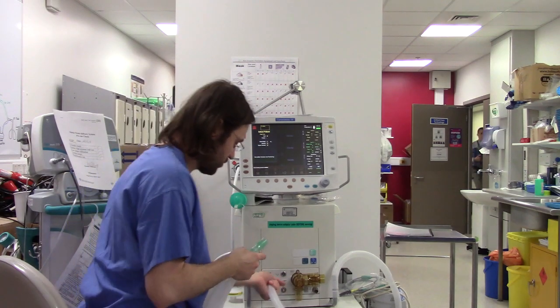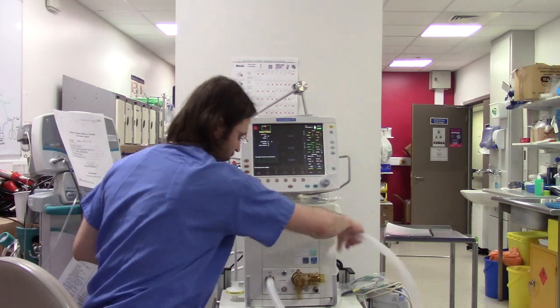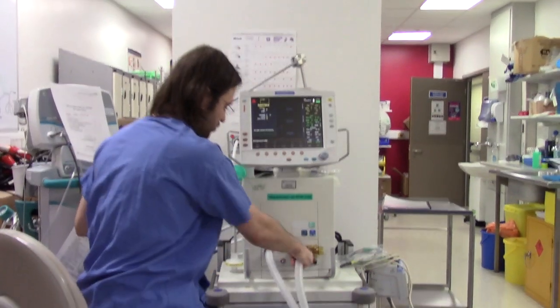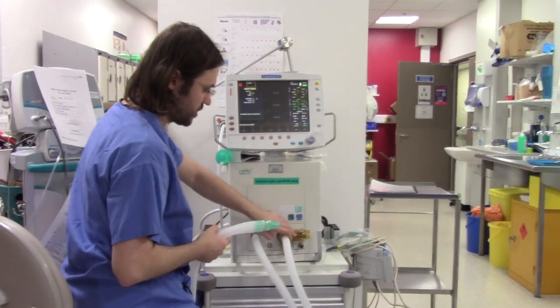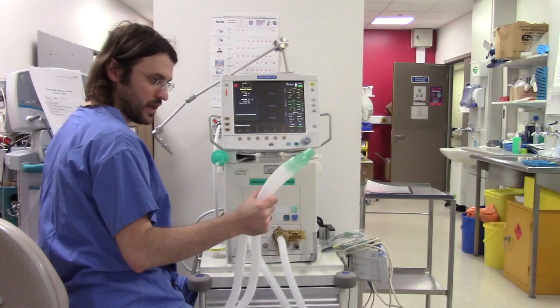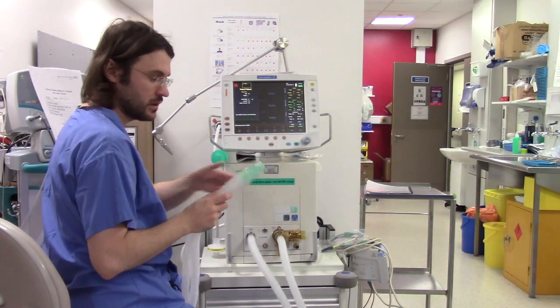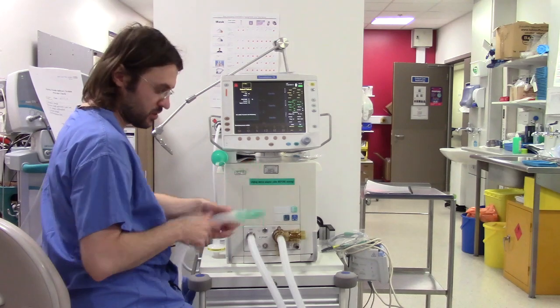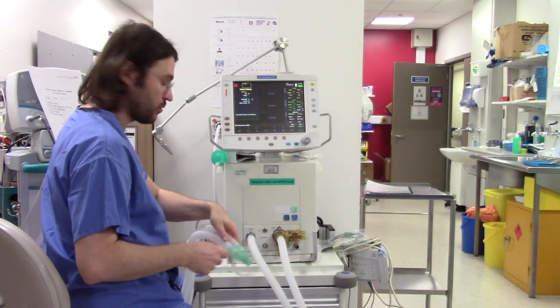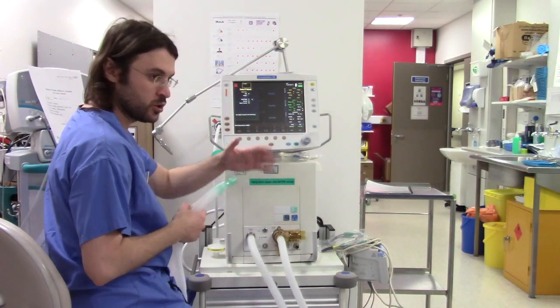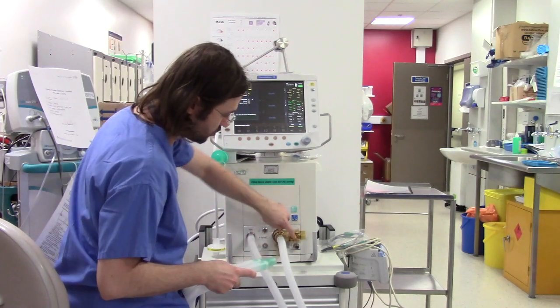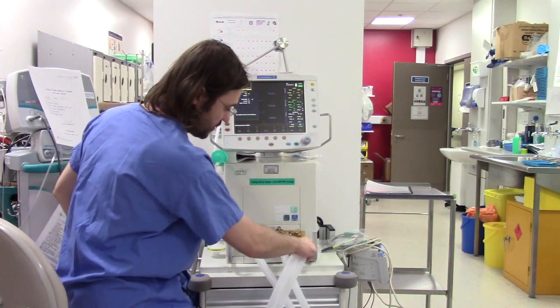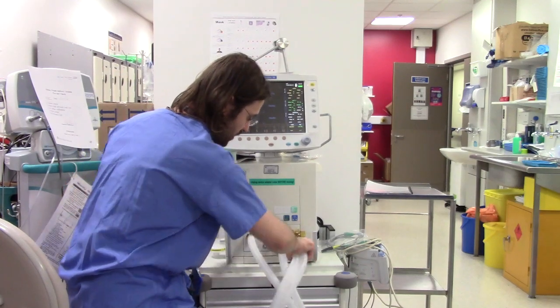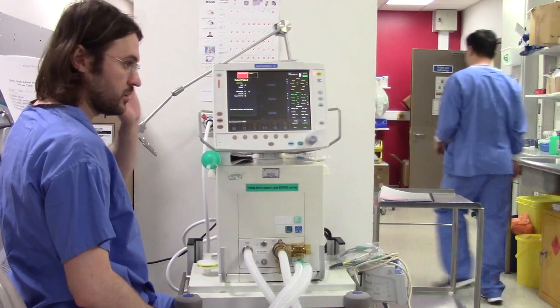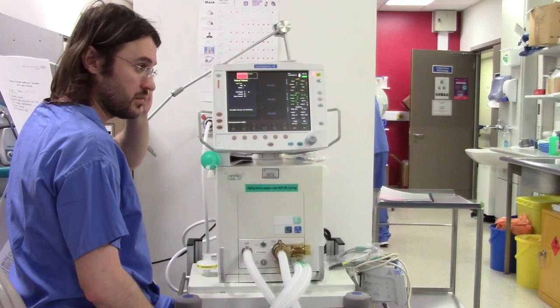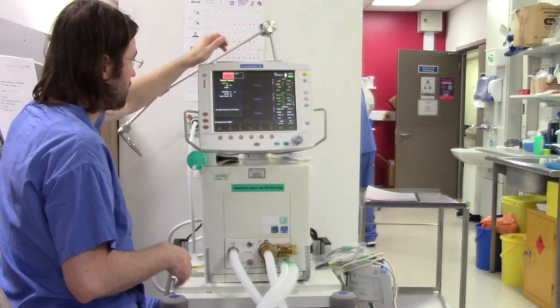Okay, so you connect one end of the tubing to inspiration, one to expiration, and the end that goes to the patient is called Y, because it has the shape of the letter Y. You'll have to occlude it, and if you want to occlude it, you can use this bit of the ventilator. You just push it in, and it's occluded. When we hear this alarm, it's a sign that it's actually occluded.